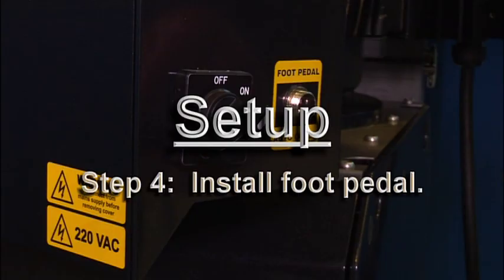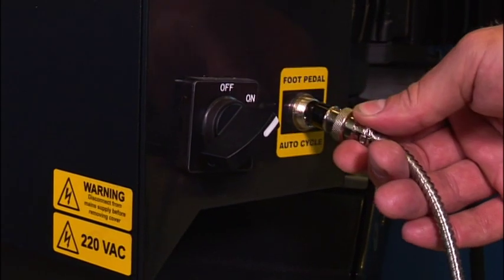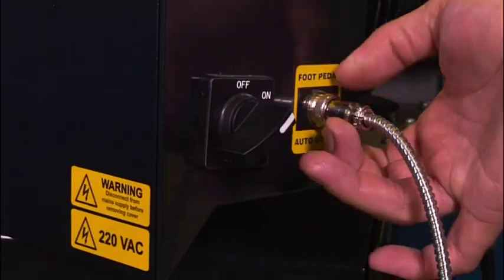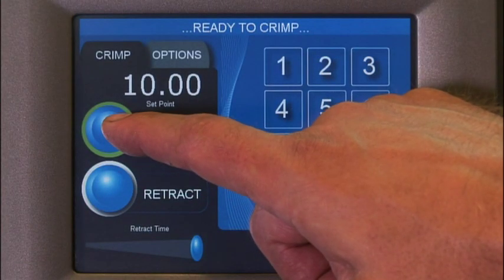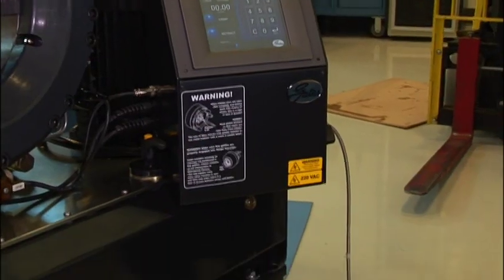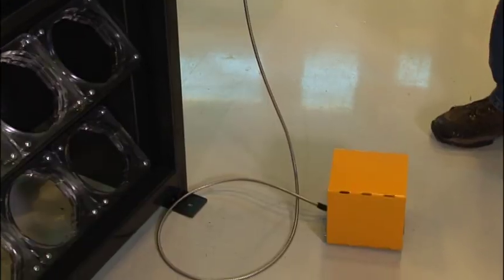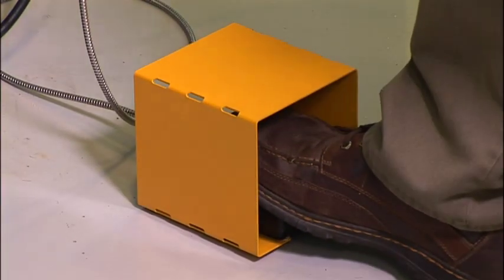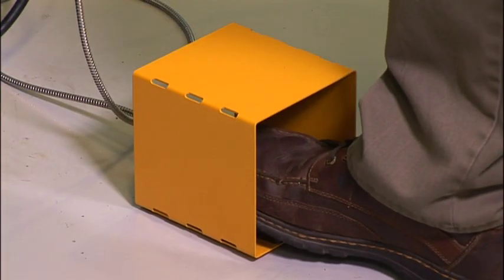Step 4. Install the foot pedal by plugging it into the lower right side of the control panel. The crimper can be activated from the crimp screen or by using the foot pedal. The foot pedal also has an auto retract feature, which is activated after the head has moved to the specified crimp diameter. The protective metal case surrounding the pedal will avoid accidental activation.